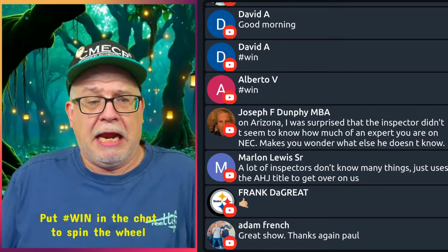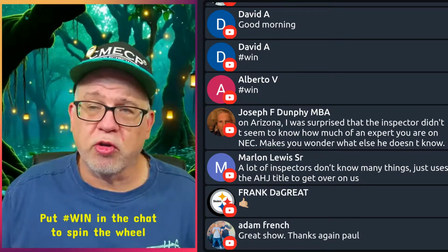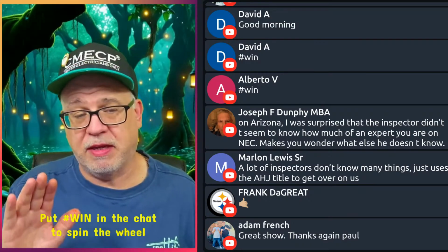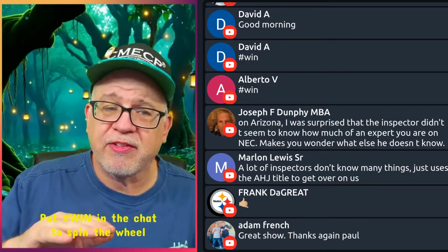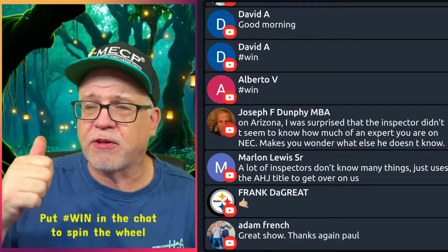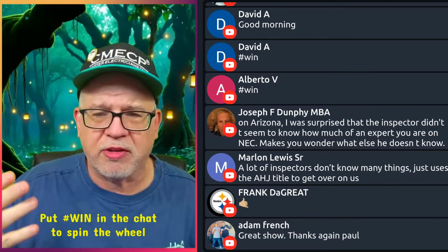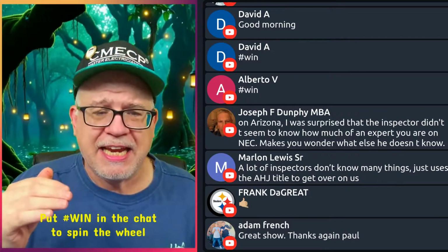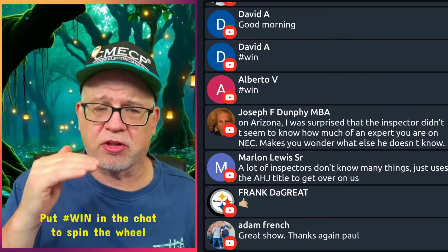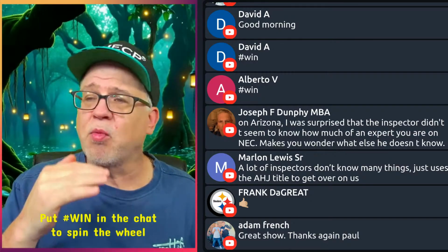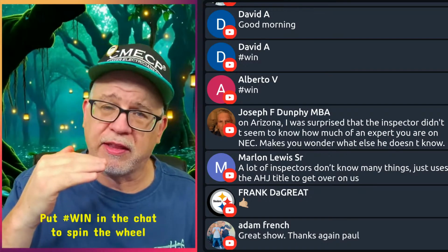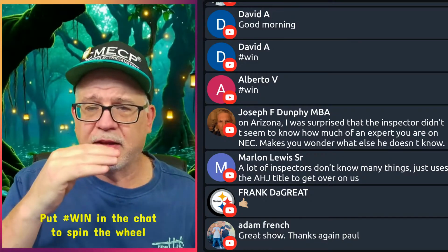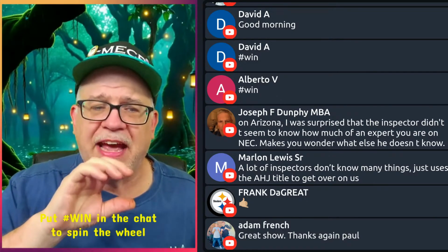Dude, relax. The small conductor rules in 240.4(D) have an allowance. There's another table here that says if you're dealing with HVAC, if you're dealing with motors, and it gives you some other options. Look, relax. If you look at that nameplate, you'll see what the running current is, and you'll see that it is more than covered. Usually it covers not only the air conditioning compressor, but also the fan motor, the condensing fan. So you'll have that value.